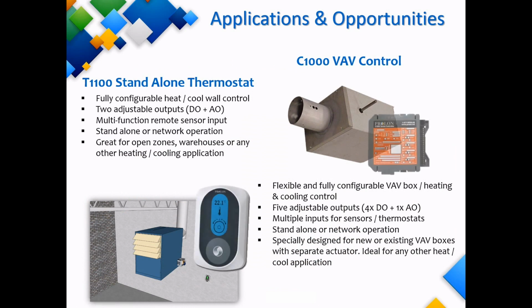Prolon offers a configurable thermostat, the T1100. It has 1 digital output and 1 analog output, and each output can be used for either heating or cooling purposes. So it could be configured as a 1 heat, 1 cool thermostat, 2 heat, or 2 cool. This device is useful for controlling equipment such as zone valves, unit heaters, and exhaust fans. The thermostat can also be used to control radiant floor applications.